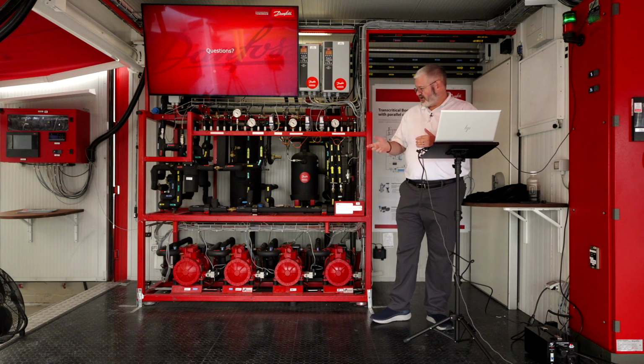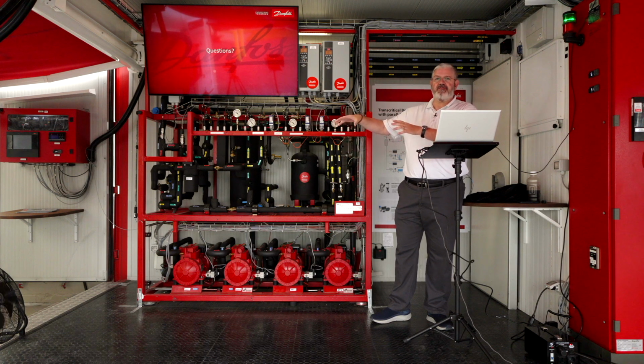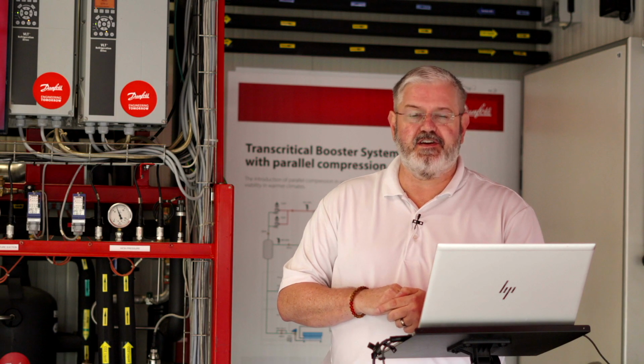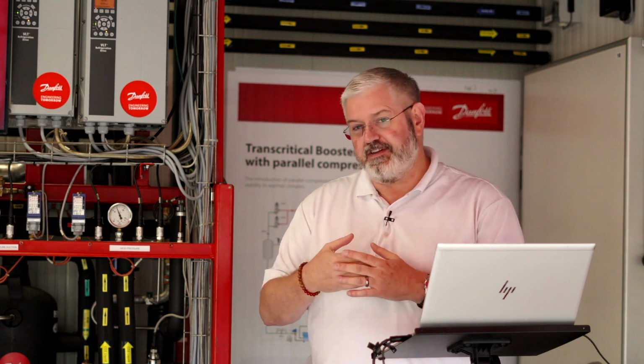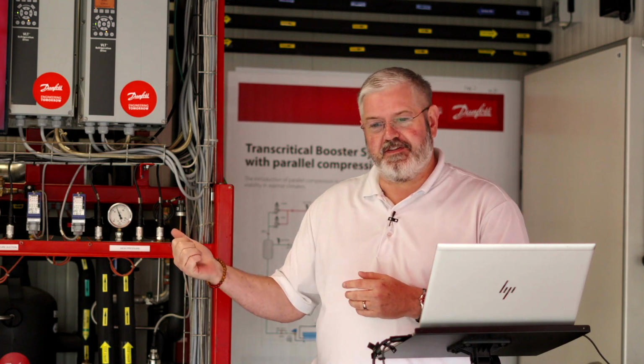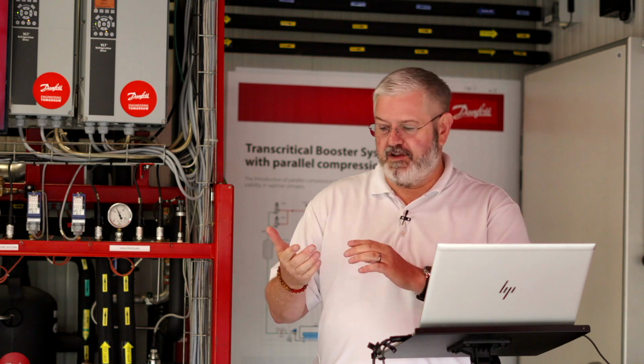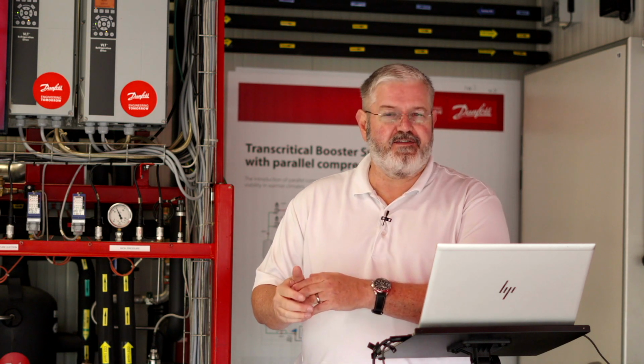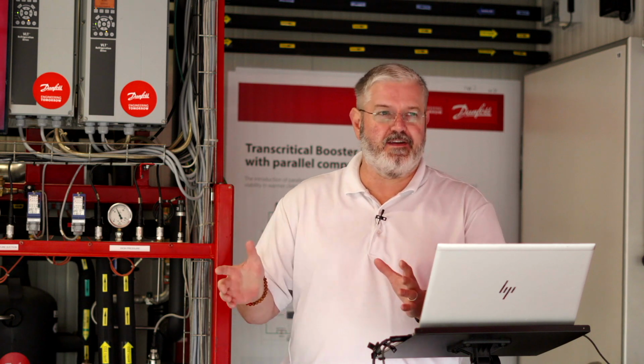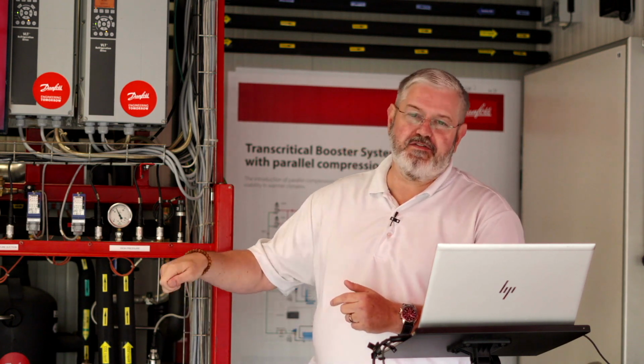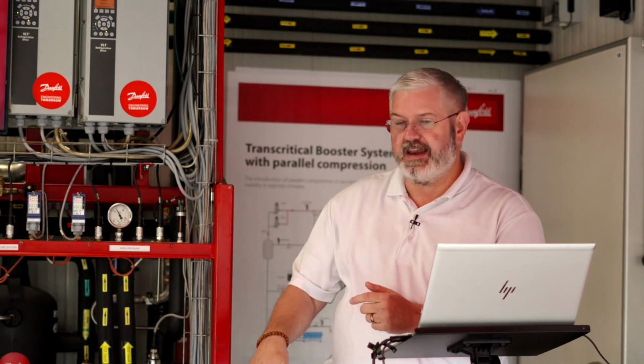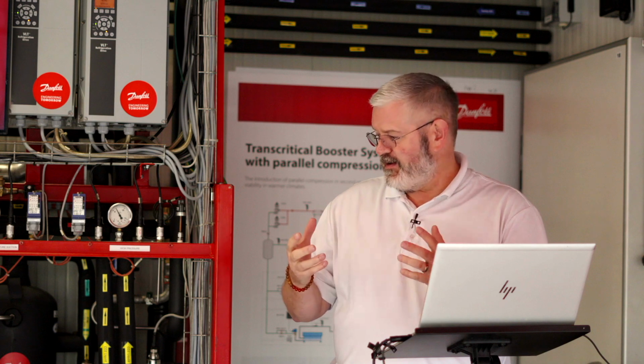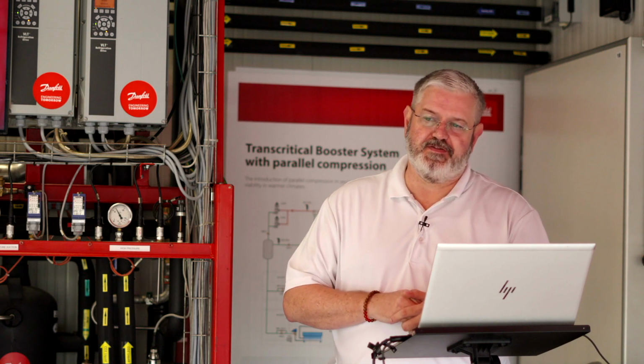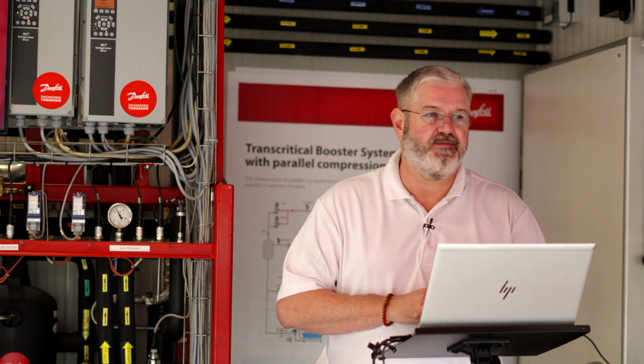I have been on sites where a vibrating compressor cracked a discharge line, so you see a little bit of a fog in the area. But safety wise, the only thing I've really seen that was dangerous was a technician looking for a leak with his hand. I personally feel that's dangerous because if you're on the discharge side of the system, that could be 1,400 pounds, and even a little pinhole is going to be a lot stronger than your skin. So I would highly recommend not looking for leaks with your hand on a CO2 system. Worst case, if you want to use that method, get a piece of cardboard and use that because you don't mind if it gets cut. Past that, I haven't seen any safety concerns as far as things rupturing and getting on technicians.